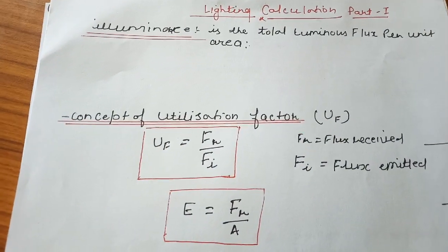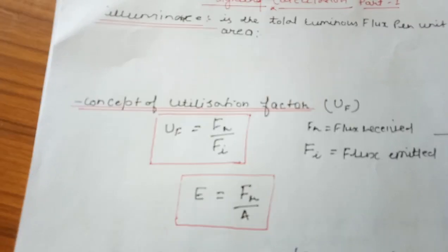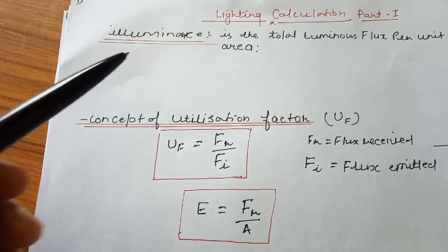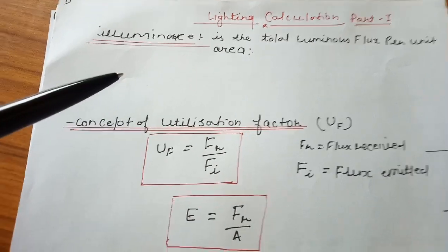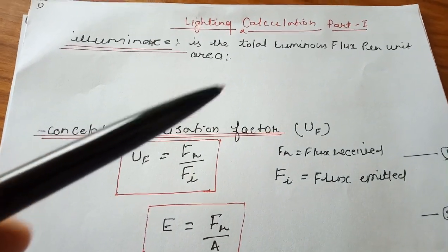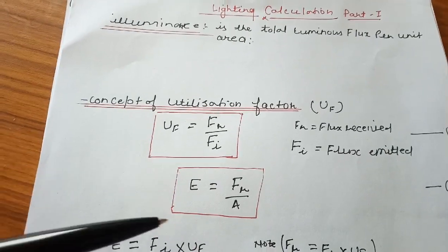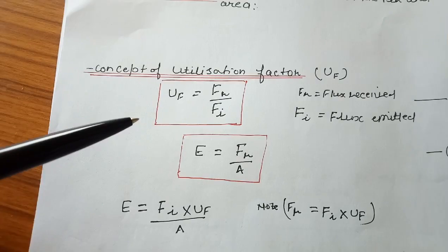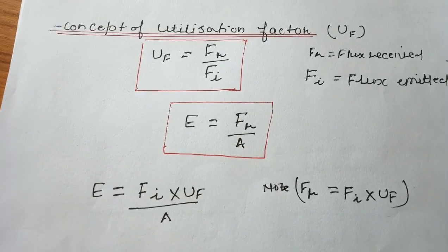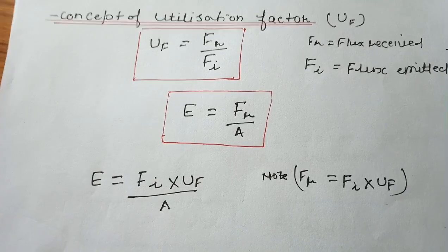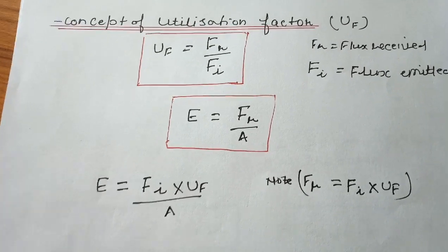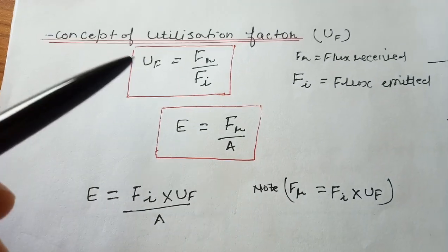Welcome to this video on lighting calculations. We will start with the different terms and components for lighting calculations. First, we'll discuss illuminance. Illuminance is the total luminous flux per unit area. To calculate illuminance, we use the utilization factor. The utilization factor is equal to flux received divided by flux emitted by the luminaire.